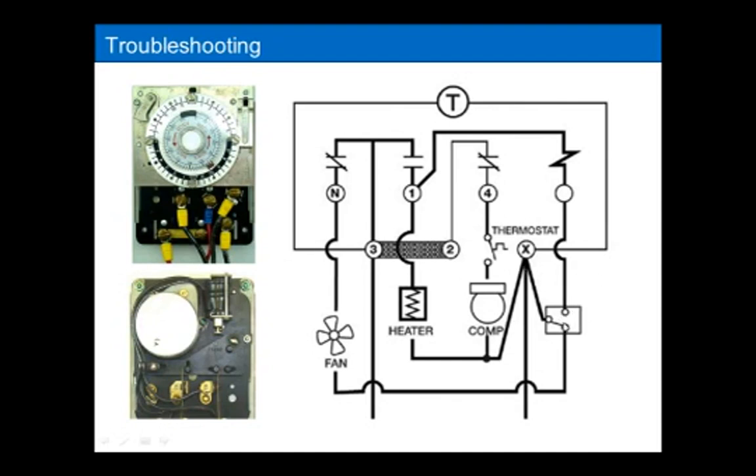is screwed up, maybe. Or if it never comes out of defrost, it just stays in defrost, maybe you have a combination of problems. So you put it in defrost and see what's going on, and that'll help you get to where the problem may lie. Because you know that it should, at one time, energize this coil and terminate defrost. If that never occurs, that may be a problem for you.